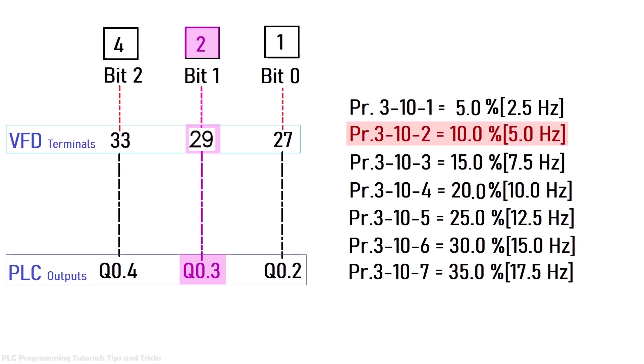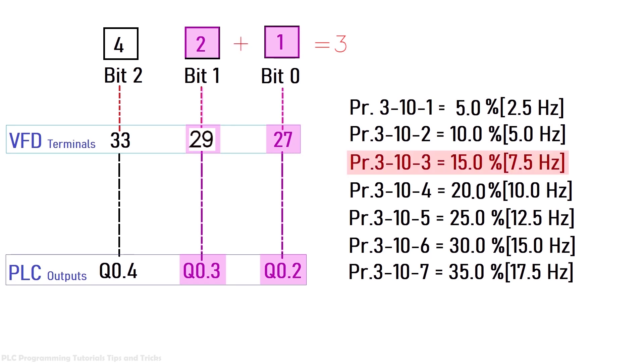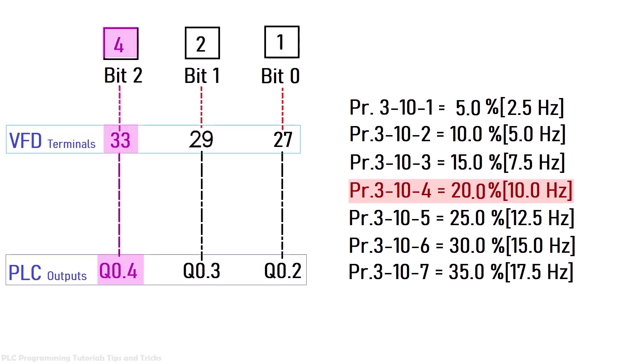If we turn on Q0.2 and Q0.3 together, it activates bit 0 and bit 1. The sum of these bits is 3, so it loads preset frequency reference 3 — 7.5 Hz — and the motor will run at 7.5 Hz. If we turn on Q0.4 it activates bit 2 (value 4), loading preset frequency reference 4 — 10 Hz.